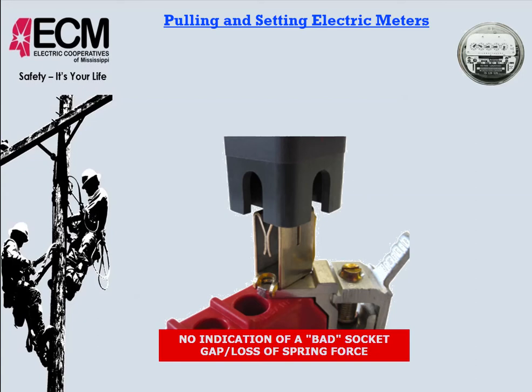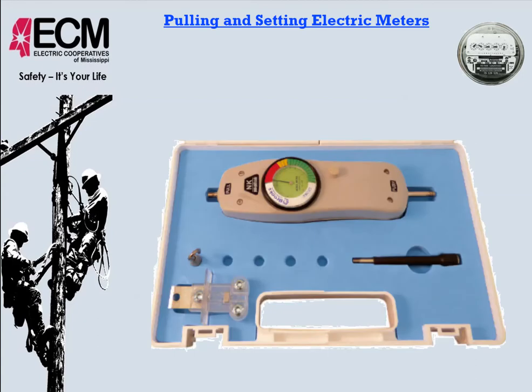This is not mandatory, but definitely a best practice. This is a different type. You see the green and the red here. So the same thing, you would connect this onto there, push it in, this flat part, into the meter socket itself, and then as you pull it back out, if we pull just a little bit to get it out, it's only going to turn the dial to the red portion. Yellow's iffy, may need some attention, but if it gets to the green, we have to pull it hard enough to get to the green. Definitely that has the proper tension on it.